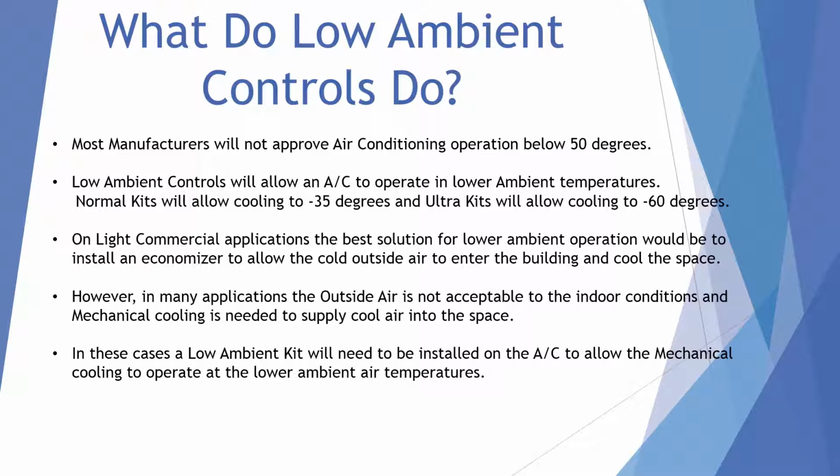On light commercial applications, the best solution for lower ambient operation would be to install an economizer to allow the cold outside air to enter the building and cool the space. However, in many applications, the outside air is not acceptable to the indoor conditions, and mechanical cooling is needed to supply cool air into the space. In these cases, a low ambient kit will need to be installed on the AC to allow the mechanical cooling to operate at the lower ambient air temperatures.